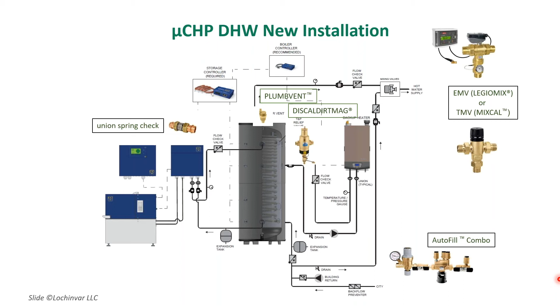In this case, we've got a wall hung boiler heater sitting here. In some cases, you may have a system with an old, 78 to 85% efficient system. They're not ready to replace it, but they want to make it last a little longer, maybe improve their efficiency. Well, we can simply front end load the system with a simple connection into the loop, bringing cogeneration into an old application.